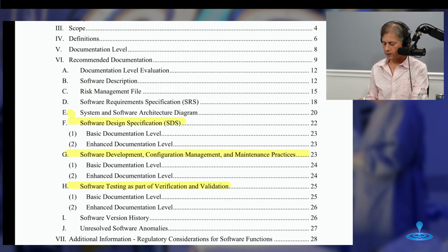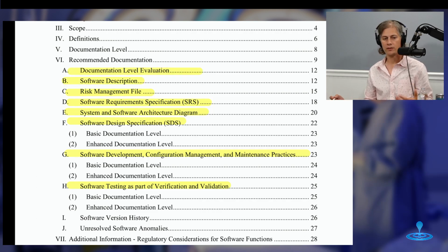Look, none of this stuff is really that unusual for software development or for medical device development. It's kind of the hybrid of what you would expect to see. What's expected out of the design controls process from FDA, including verification and validation? Cool. How does that merge with typical software development practices? Things that you don't see from most other parts of a medical device, like a software requirement specification, an architecture diagram, design specification that are software specific. So if you just take those two things and merge them, you're going to see a lot that you're expecting to see.